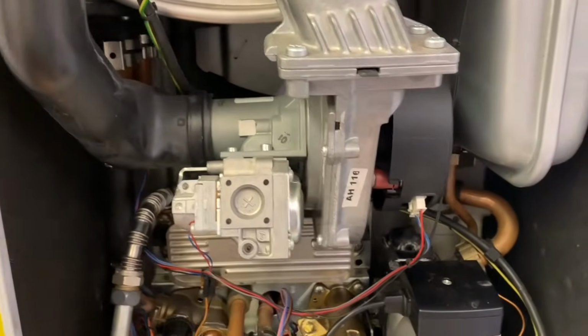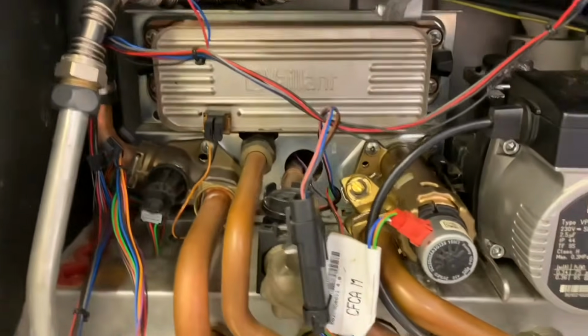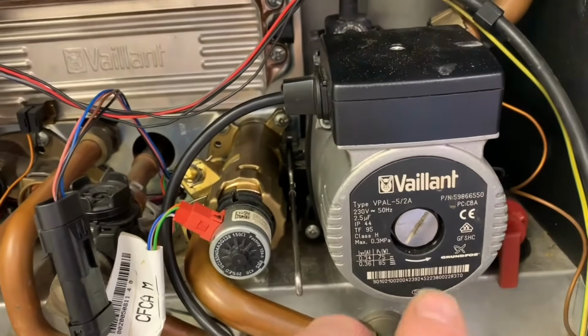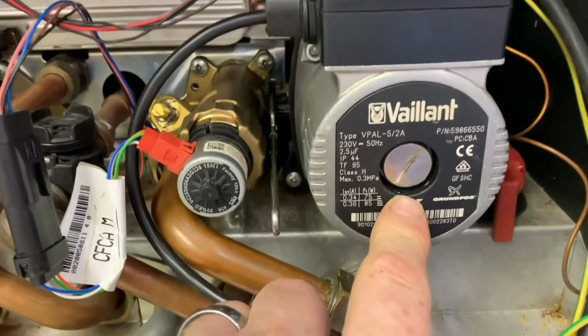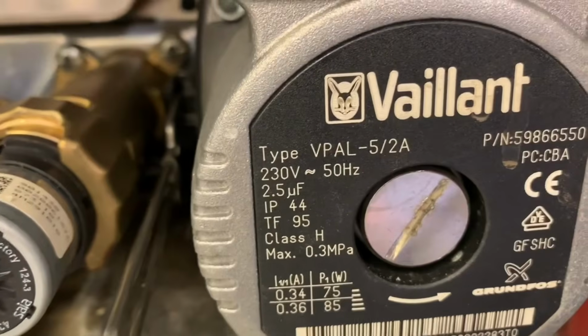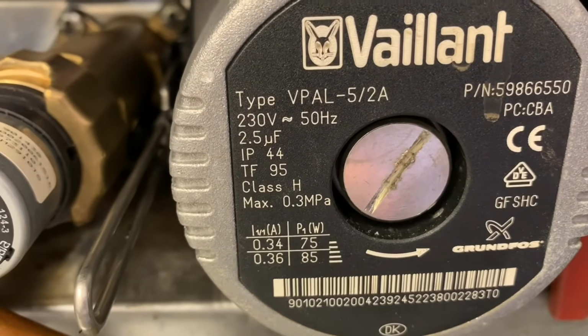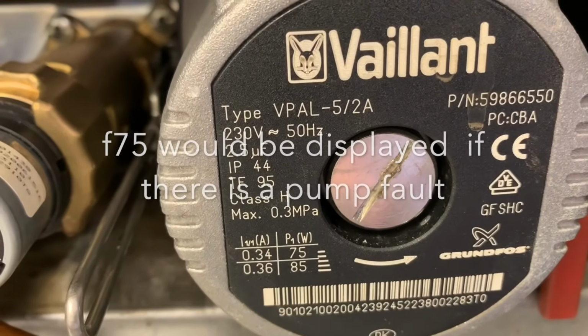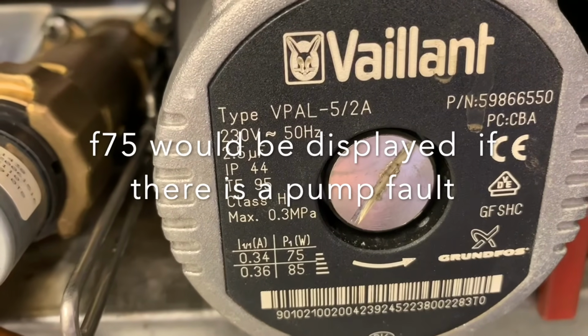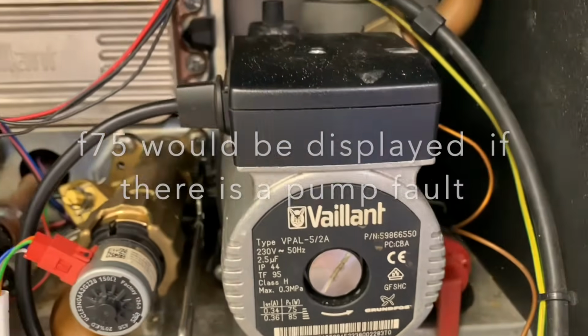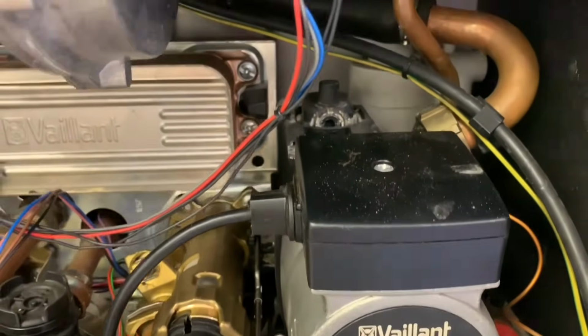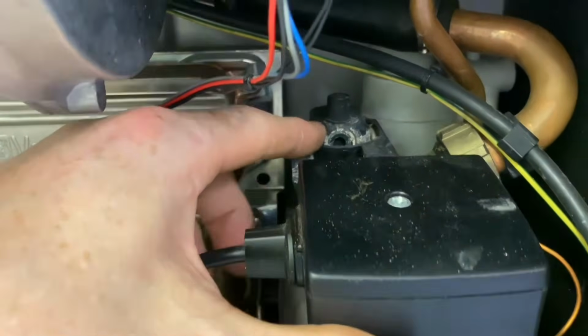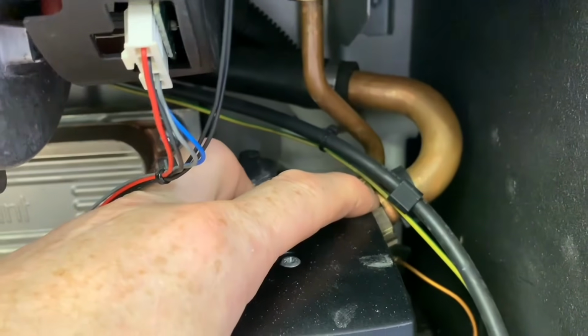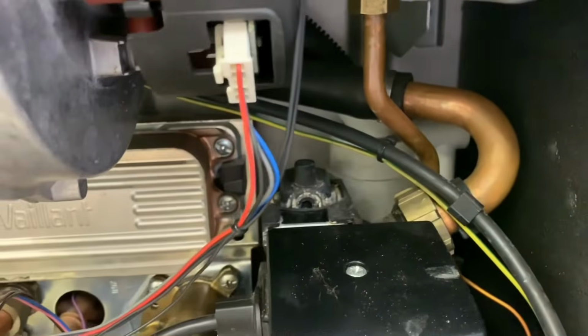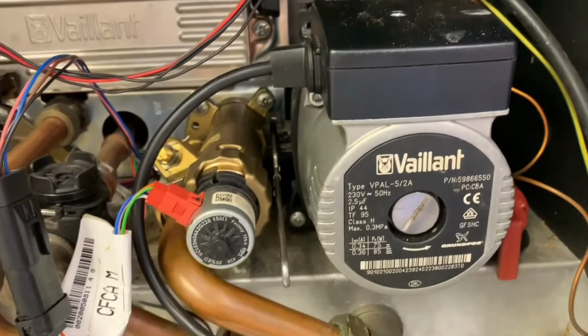So as we come further down, we come into the water set. So let's start on the right hand side. This is our pump. If you have a look at the pump closely, you can see it's made for Vaillant by Grundfos. So it's a special pump. You can't just put any Grundfos pump on there. Behind there, what you can see where it's been leaking is the auto air vent on the back of the pump. And then this is the return pipe going up to the heat exchanger. When we take the burner door out, you'll see that more closely.